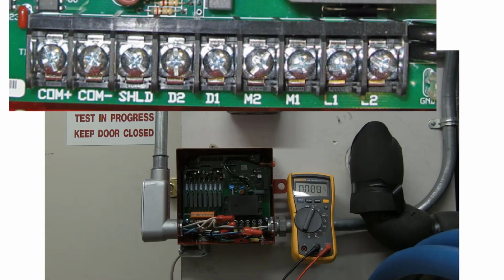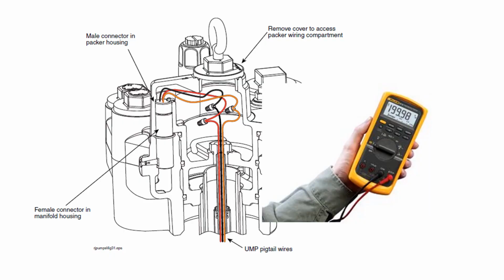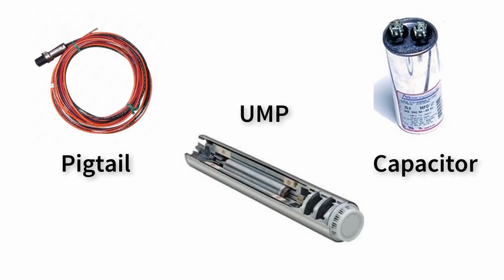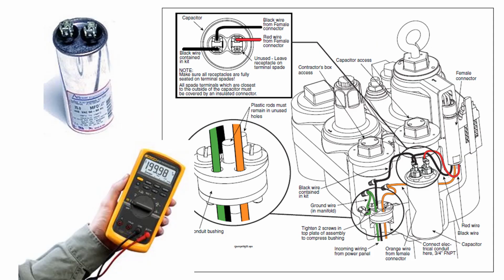To verify field wire, tie M1 and M2 together and go to the contractor's box at the pump and measure the resistance of the field wiring. It should read a low resistance. If the field wire is good, the issue could be the pigtail, capacitor, or UMP. Measure the capacitance of the capacitor and verify the wiring.